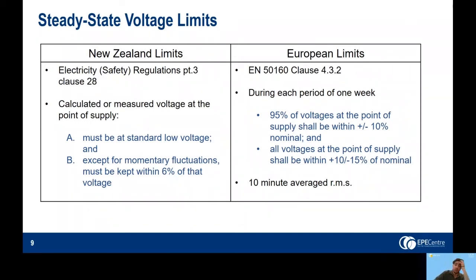These can be contrasted with the European limits, which are defined in EN 50160, clause 4.3.2. These state that during each period of 1 week, 95% of voltages at the point of supply shall be within plus or minus 10% of nominal, and all voltages at the point of supply shall be within plus 10% minus 15% of nominal. And it explicitly states that these are based on 10-minute averaged RMS voltages.